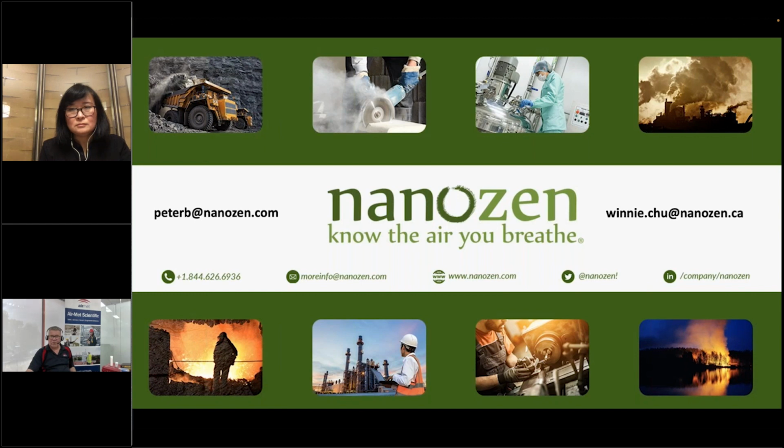Okay. Does the Nanozen require a software package to upload and retain data? No. There is a software, but everything is saved in the monitor, or you can download into an Excel file, or use the software. Three different options. It always stores the data in the device. Then, at the end of the test or during the test, you can pass the data to a software package that we have that will graph it for you or send it to an Excel file. Or it can automatically send it to a location in a computer file that can be constantly read by an automated system.